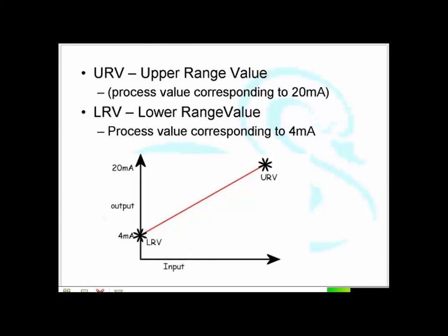Most modern gauges are, to all intents and purposes, just computers nowadays. So with modern gauges, we just communicate with them. We plug our laptop in, and modern gauges on the whole give out a 4 to 20 milliamp signal. So we say, okay, when this comes in, we want you to give 4 milliamps, and when this comes in, we want you to give 20 milliamps.